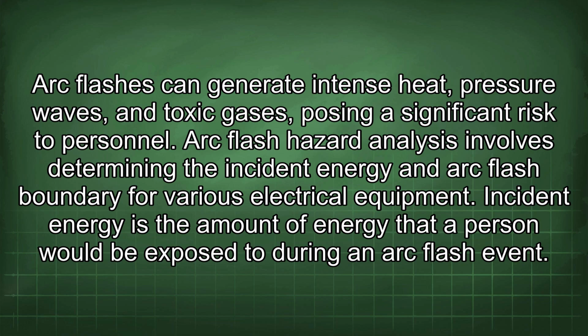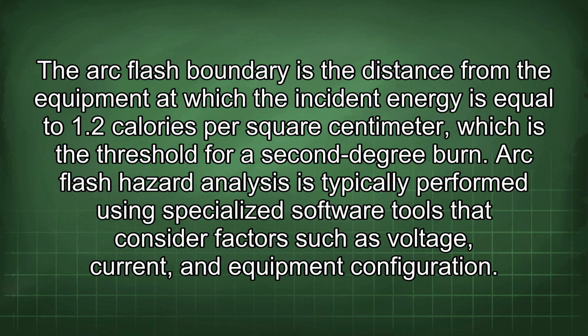Incident energy is the amount of energy that a person would be exposed to during an arc flash event. The arc flash boundary is the distance from the equipment at which the incident energy is equal to 1.2 calories per square centimeter, which is the threshold for a second-degree burn.